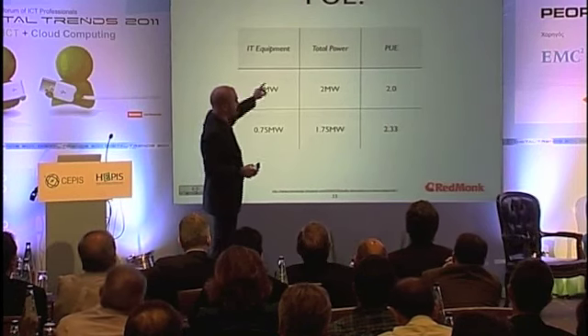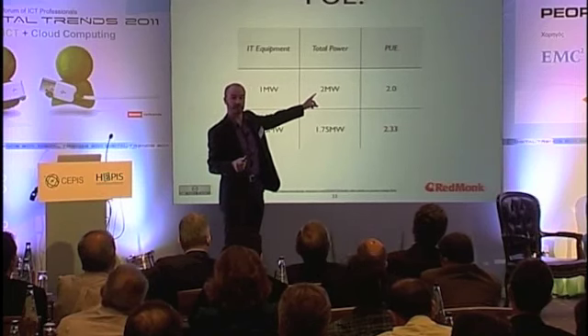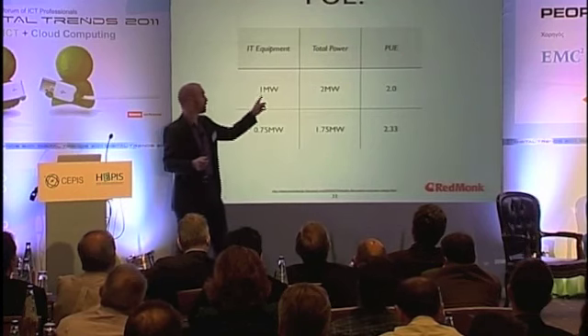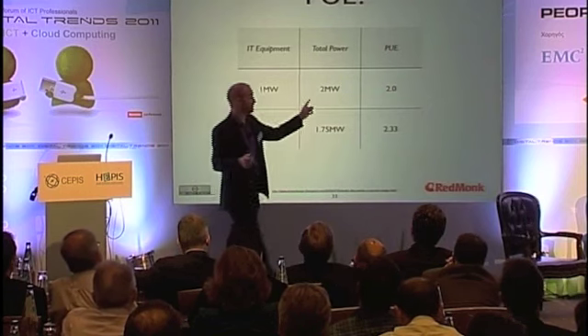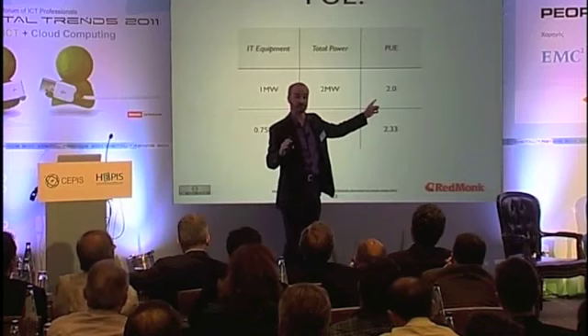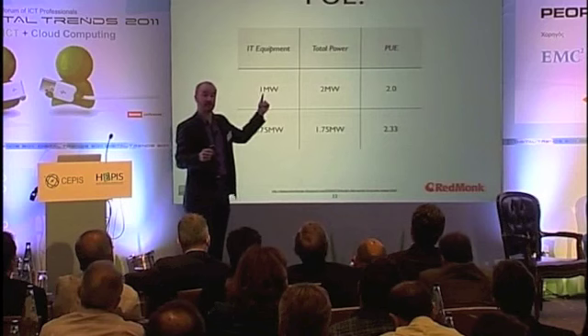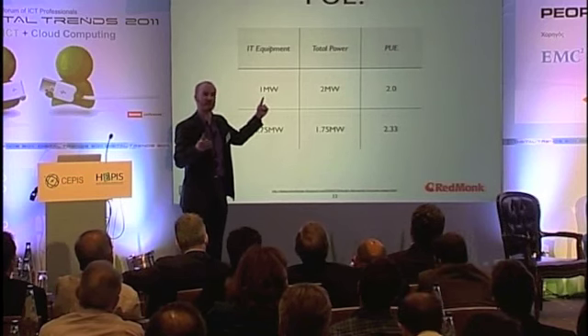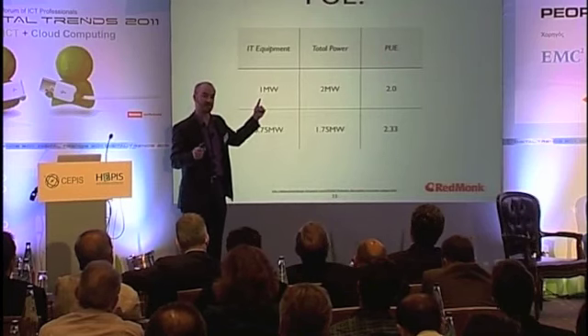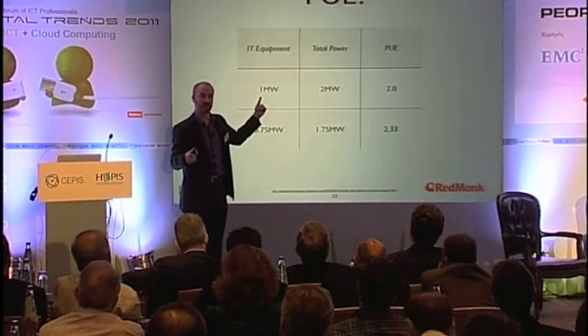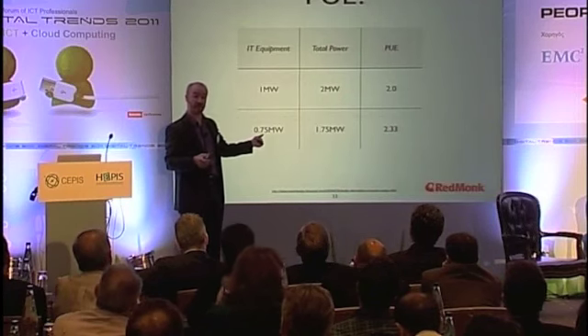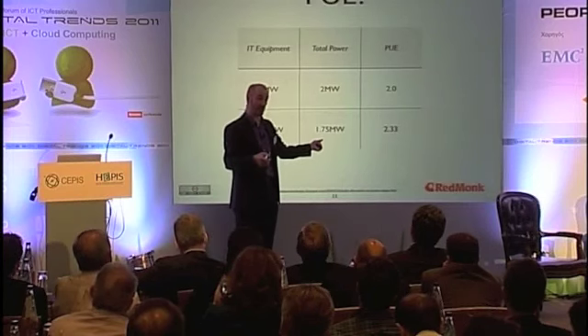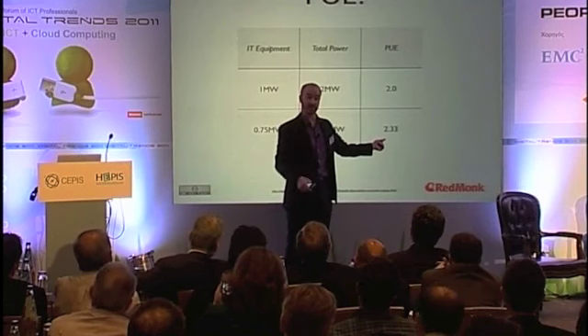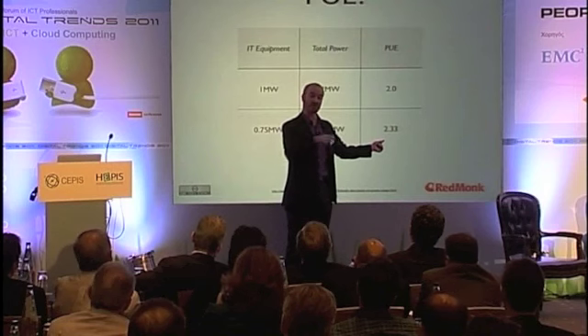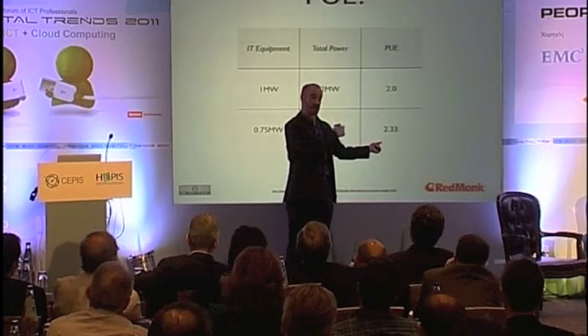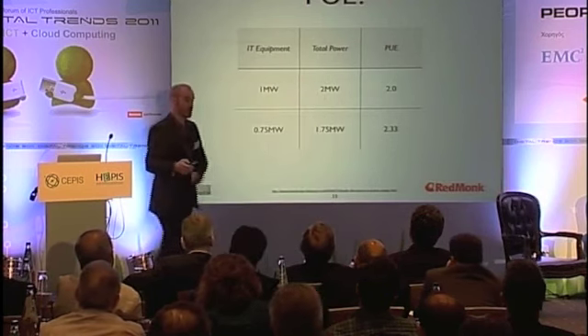Take a quick look at this graph here. If I have a data center which takes in 2 megawatts of power, and of those 2 megawatts, 1 megawatt goes to powering the servers, then I have a PUE of 2.0. Very simple. However, if I realize that my 1 megawatt isn't being used very efficiently, and that some of my servers are being underutilized, maybe I virtualize some of them and shut some of them down, then my power draw from my IT equipment drops to 0.75 of a megawatt. My total draw drops to 1.75, and my PUE goes up to 2.33. Remember I said PUE closer to 1.0 means you're more efficient? I've actually made it more efficient, and my PUE has gone from 2 to 2.3. So that's a huge problem right there with the PUE metric.